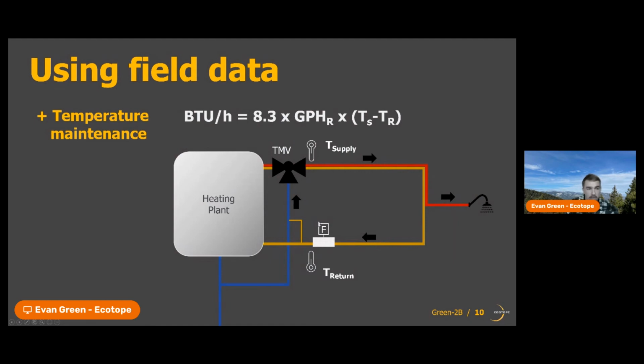So using our basic heat equation, we're going to need to plug in a temperature differential as well as the overall flow from this temperature maintenance loop. The temperature differential is going to be the difference between the temperature that's supplied from the mixing valve and the temperature that's returning to the heating plant. And then the flow, we can capture the overall flow returning to the heating plant, because we might have a lot of different branches coming off. I have a simplified loop drawn here, but we might have several branches, but they all come back together before they enter that heating plant in a typical case.